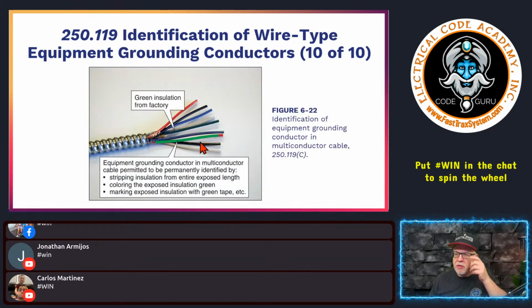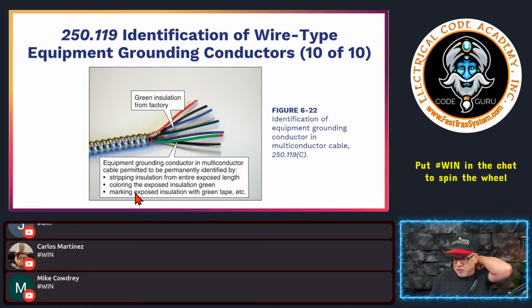All right. So here you go. This is a good example. See right here? This is green insulation from the factory, right? And this one says an equipment grounding conductor in a multi-conductor cable is permitted to be permanently identified by stripping the insulation from the entire exposed length, because this is showing you have that option. Or coloring the exposed insulation green, or marking exposed insulation with green tape, that type of thing. So you have some options there.